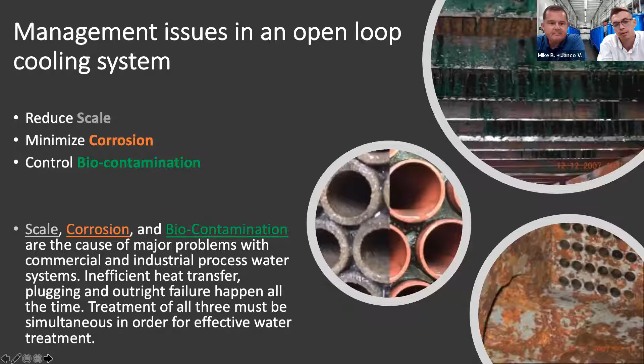So what we're doing a little bit differently, instead of using traditional chemical treatment, we're actually using what we call our dynamic scale reactors, or DSRs. These DSRs use partial electrolysis to basically pull scale into our reactors where we can control it. We're mitigating corrosion by keeping a more concentrated calcium process inside the process water itself, and we're generating the active biocide, chlorine and hypochlorous acid, from the water itself using that partial electrolysis.